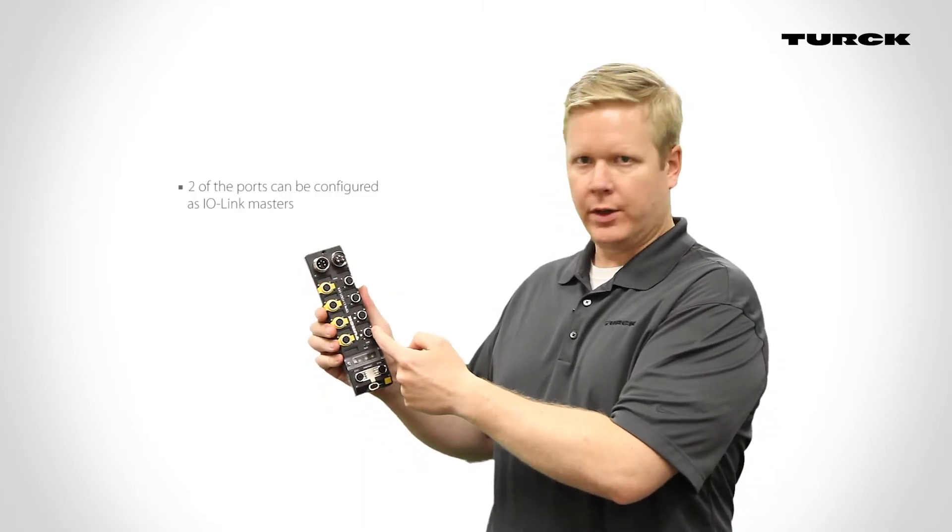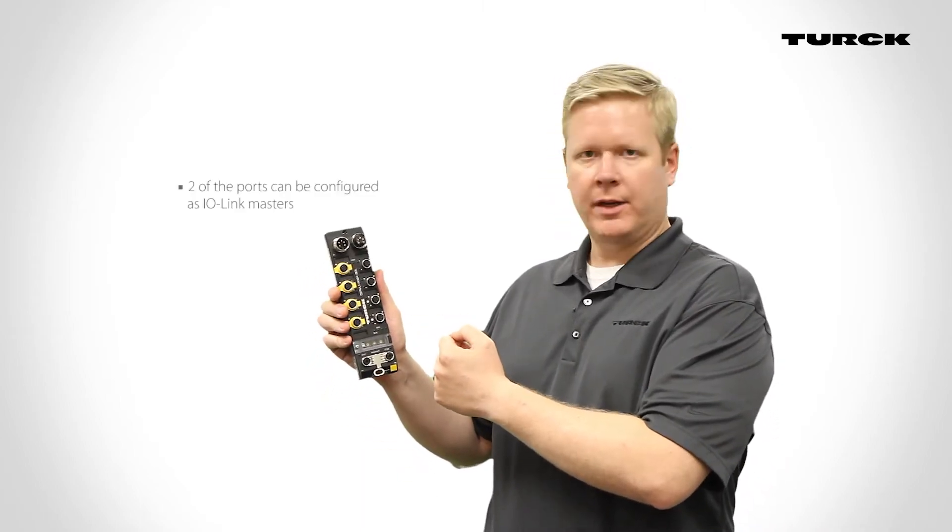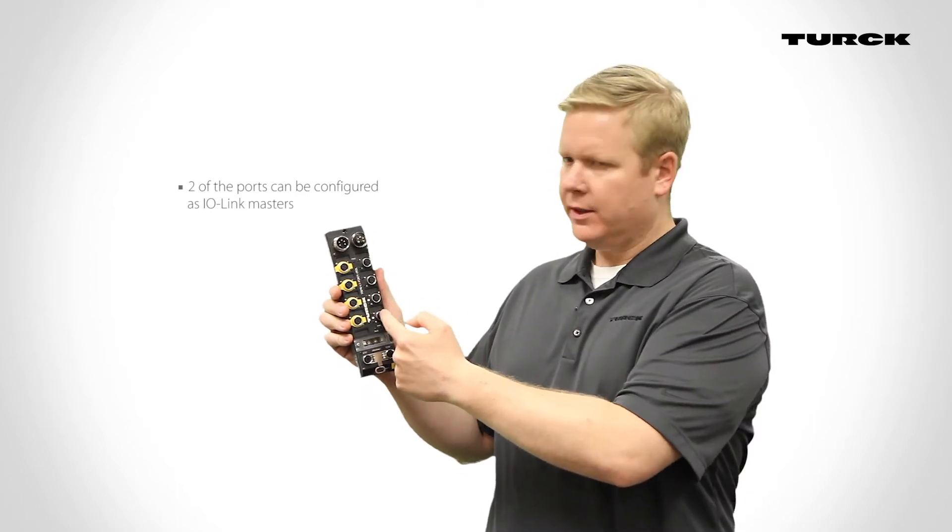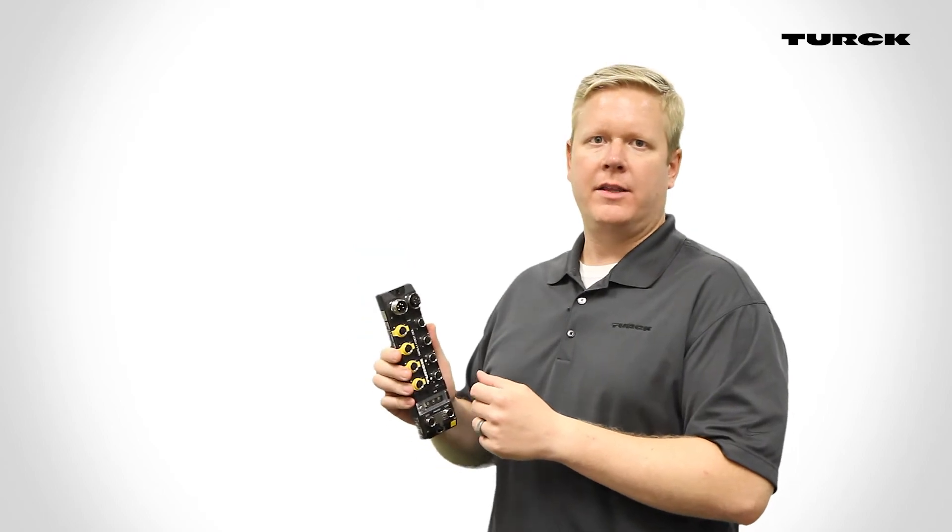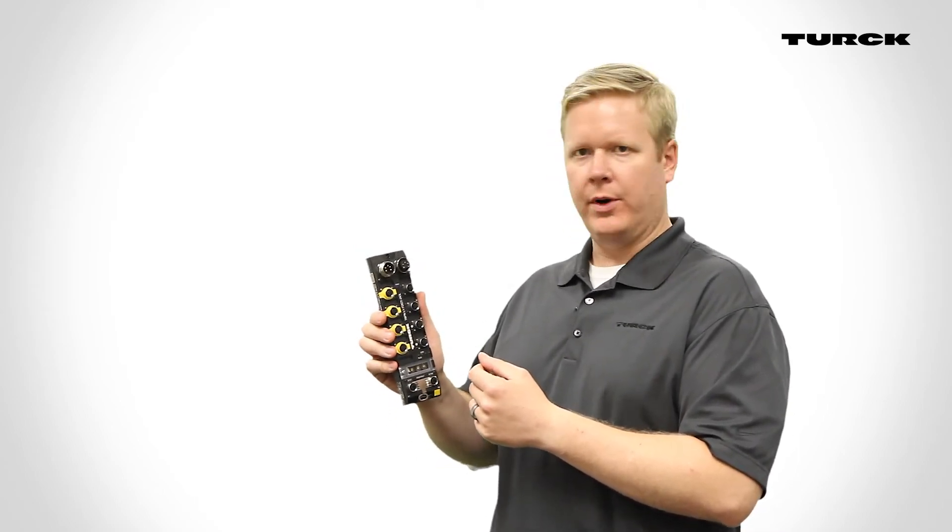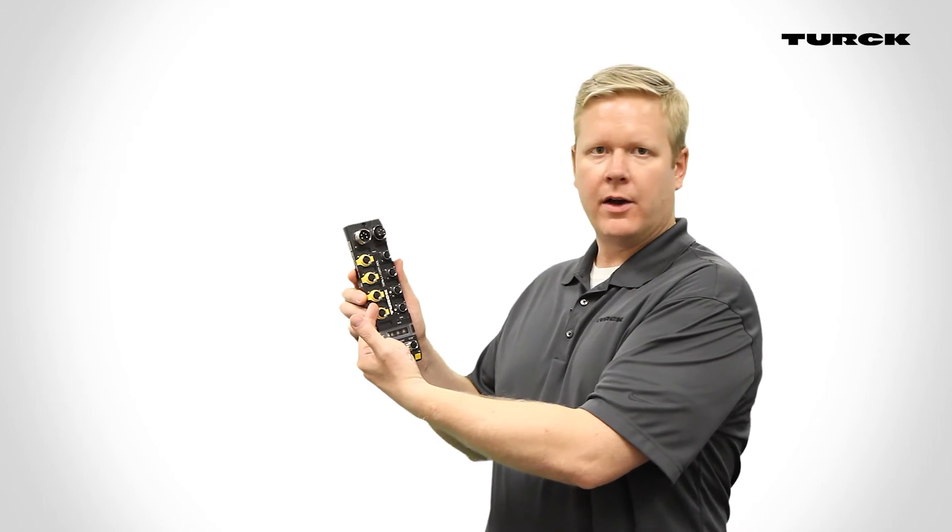If these four general purpose I.O. ports are not enough for a particular application, two of the ports can be configured as I.O. link masters. Configuring these ports as I.O. link masters, used with Turck's TB-IL I.O. link hub, which allows for up to 16 digital inputs or outputs, gives a single PROFISAFE block the ability to have up to 36 general I.O. points in addition to the safety I.O.